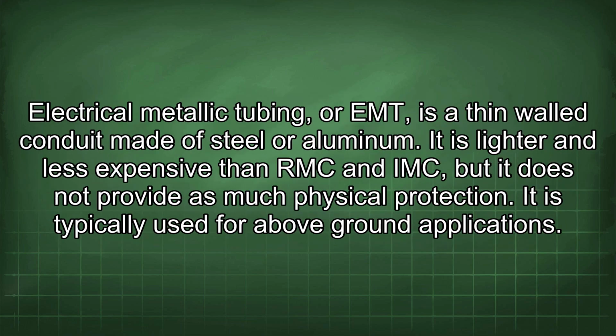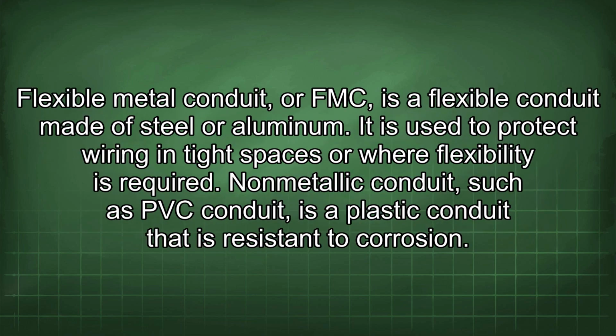Electrical metallic tubing, or EMT, is a thin-walled conduit made of steel or aluminum. It is lighter and less expensive than RMC and IMC, but it does not provide as much physical protection. It is typically used for above-ground applications. Flexible metal conduit, or FMC, is a flexible conduit made of steel or aluminum. It is used to protect wiring in tight spaces or where flexibility is required.